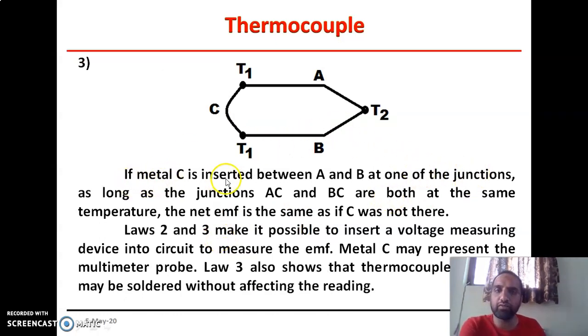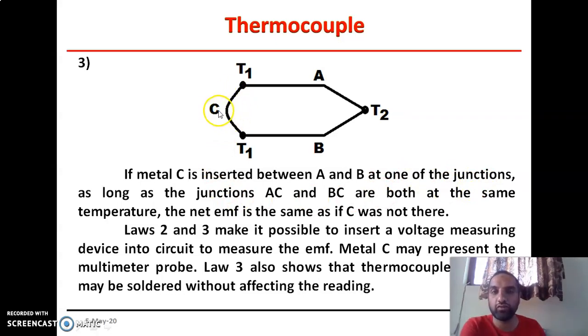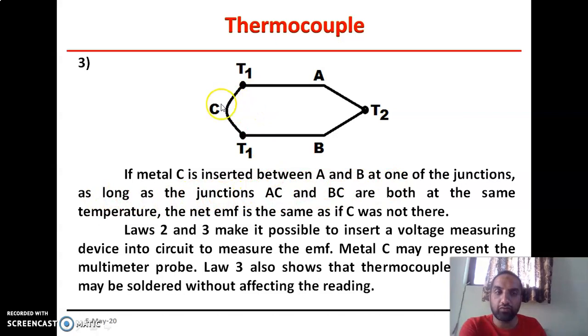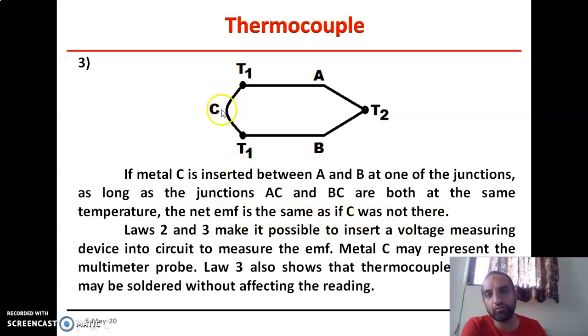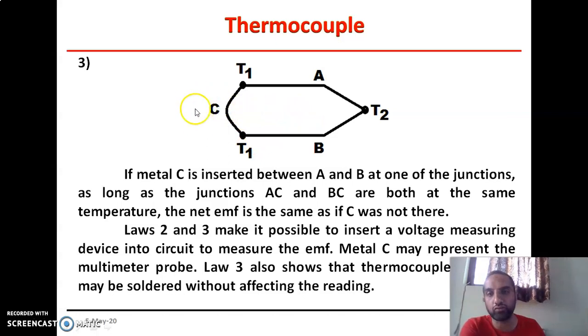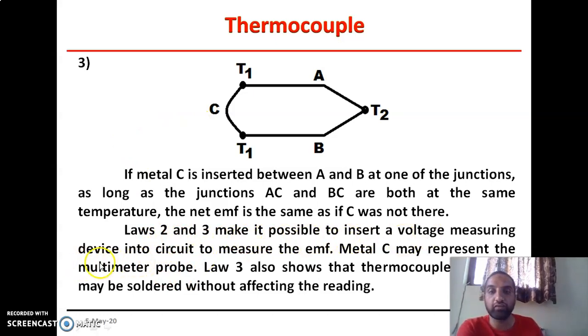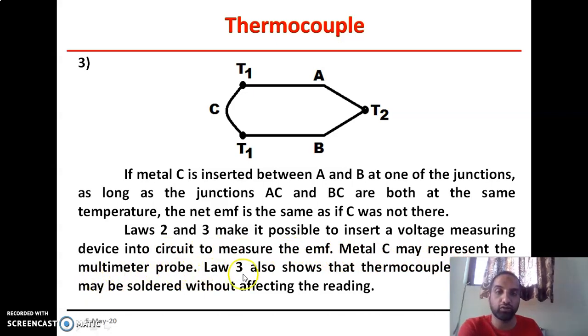The third law states that if metal C is inserted between A and B at one of the junctions, forming two junctions CA and CB, as long as those junction temperatures are the same, the net EMF is the same as if C was not there. In short, when C is inserted at one junction where both temperatures at AC and CB are equal, there is no effect on the produced EMF. Laws 2 and 3 together make it possible to insert a voltage-measuring device like a voltmeter into the circuit. Metal C may represent the multimeter probe, and law 3 also shows that a thermocouple junction may be soldered without affecting the reading.